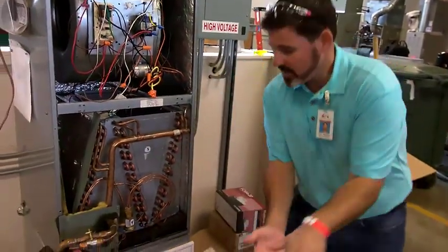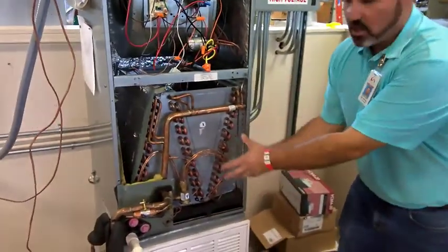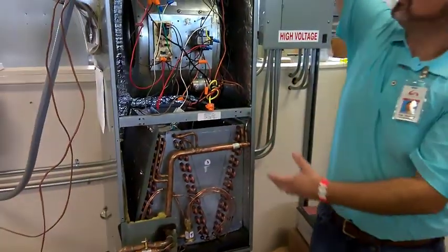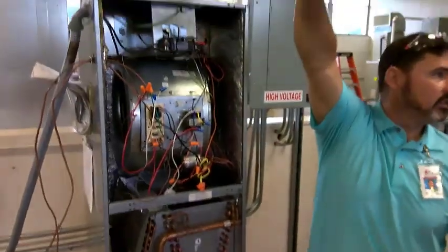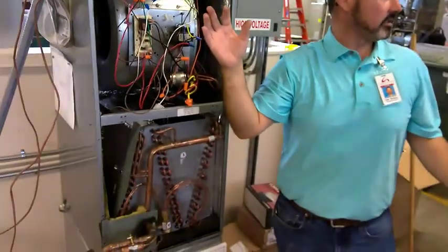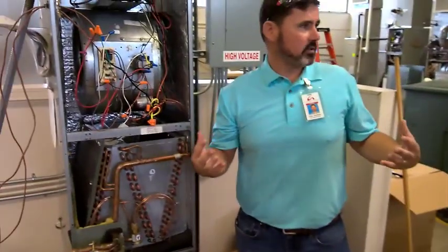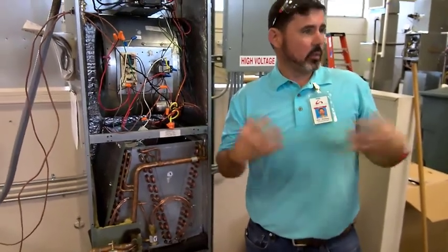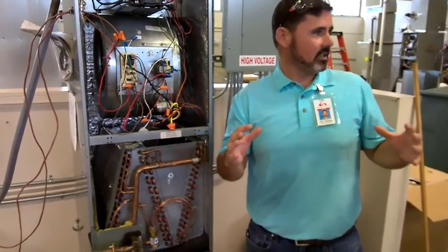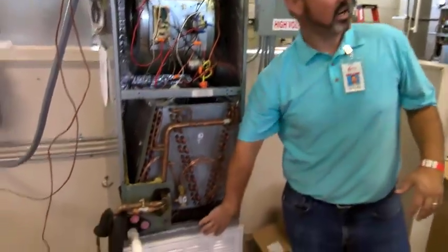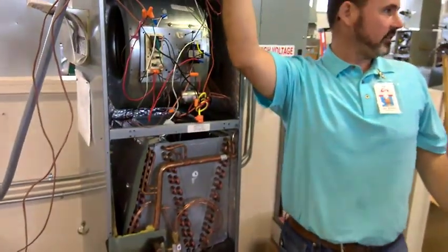That's how we go in at about 75 degrees. We blow across this cold coil. It's absorbing heat. We come out of my supply at about 55 degrees. If I'm going from 75 to 55, that's a 20-degree temperature difference. We in the industry call that our delta T. Right? That's how much our temperature changed from when our air went in until our air came out.